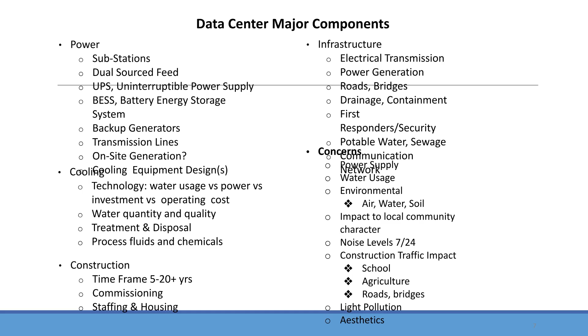Cooling is the next thing, and there's different technologies in cooling, with water being a big thing, and I've got to try to get to that. Construction can be 5 to 20 years. Commissioning can take months, and there's going to be a lot of activity there. And of course, you've got staff - it could be 1,500 people when they're first building, the first phase, and they usually build in phases. Infrastructure - there could be a big demand on the public infrastructure: roads, power, generation, distribution, and that. And all the concerns I have listed up there, everybody else is going to kind of talk about.